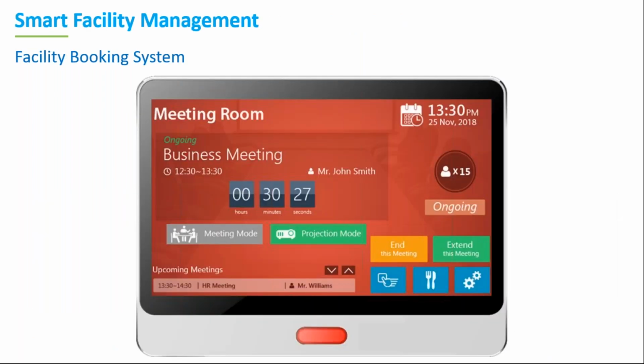We also have a fully automated facility booking system. This helps a lot in reducing unmonitored air conditioning and lighting being switched on. Based on the bookings, the software automatically switches off all the electromechanical equipment after a grace time, without any human intervention. It also switches on the aircon and lighting 10 minutes before, to bring the facility to the right temperature. It's fully automated, so if people don't check in, it automatically switches off as well, ensuring there is no unmonitored usage.